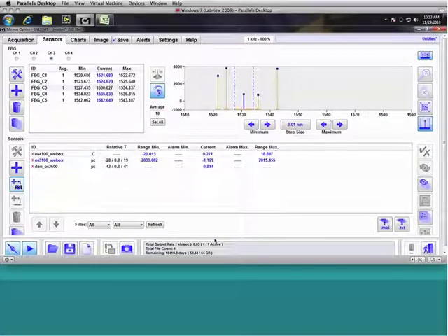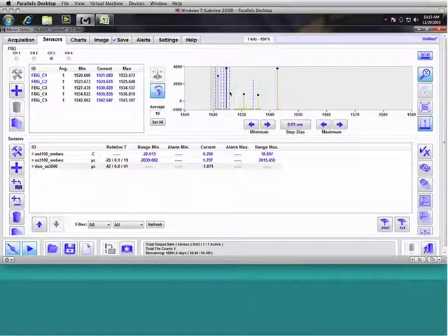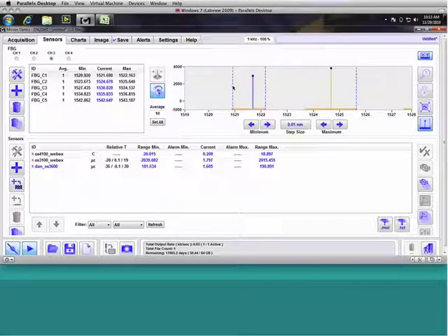Right. Okay, now with the same visual cues, we can click on the Dan 3600. We see in blue, that's our strain FBG. Indeed. And we see in gray, that's our temperature compensation FBG. And so now we can zoom in and make the appropriate changes. Since we're doing a lab demonstration, we know we're not going to see a tremendously wide temperature range. We're going to go ahead and narrow our operating temperature range of that FBG. Notice as I'm pulling these bin widths, it's changing the minimum on the table for the FBG, and it's also changing the relative T for this OS 3600. So I'm going to drag that in to be plus or minus 20.